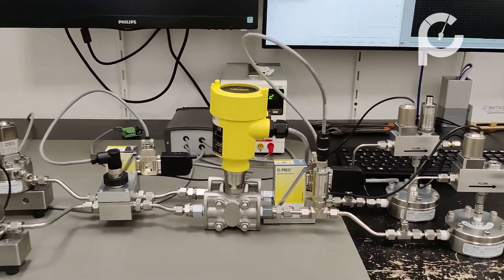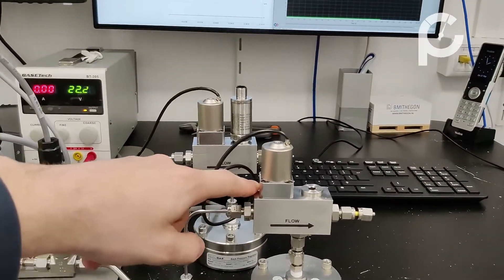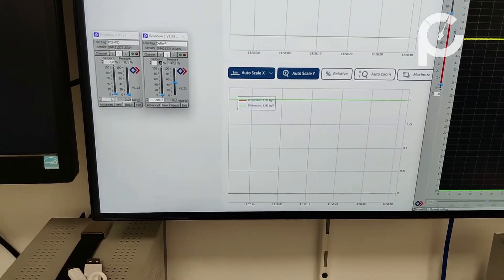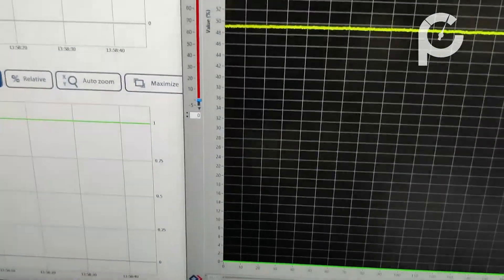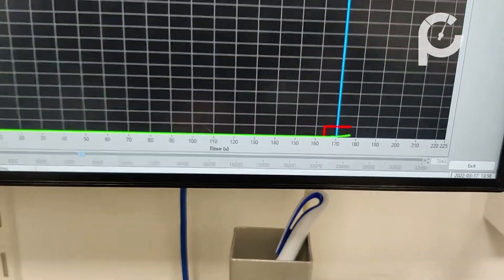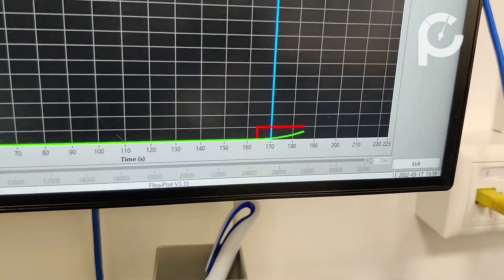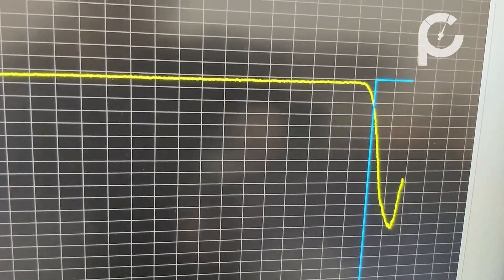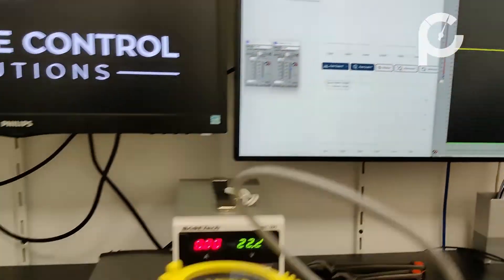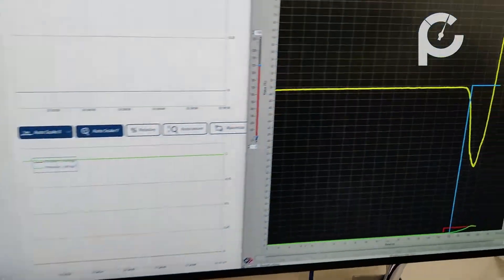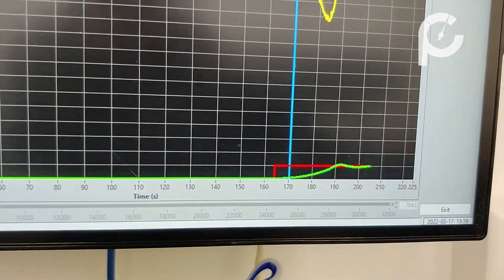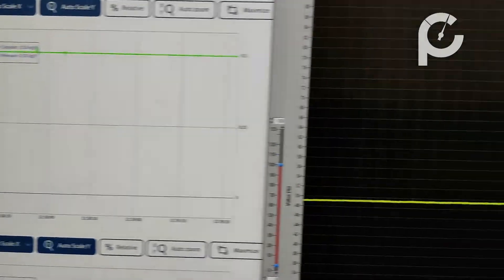I can increase the pressure inside of the system by giving a setpoint to this DRC through the software. Let's go to two percent, and also give a setpoint of 50 percent to the delta P controller. The green line is the process pressure measured by this sensor, the red line is the setpoint for the process pressure controller, the yellow line is the delta P measured by this sensor, and the blue line is the setpoint for the delta P controller.